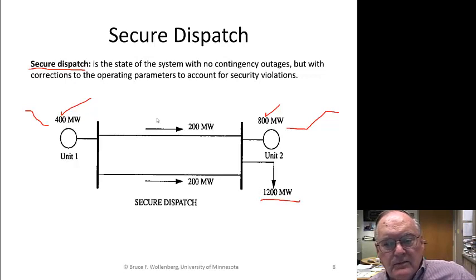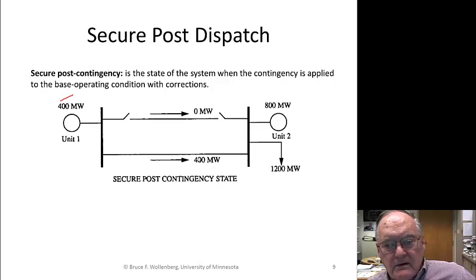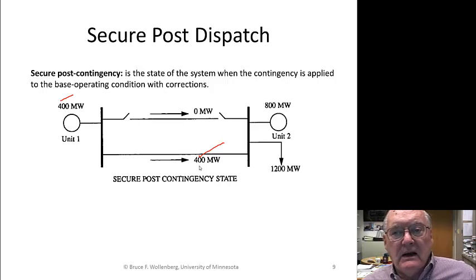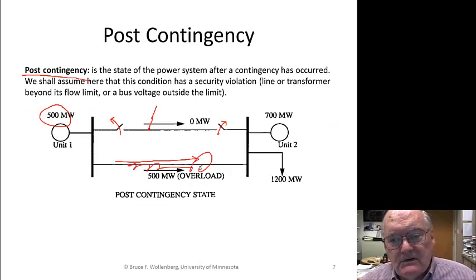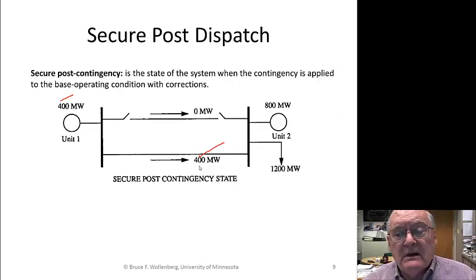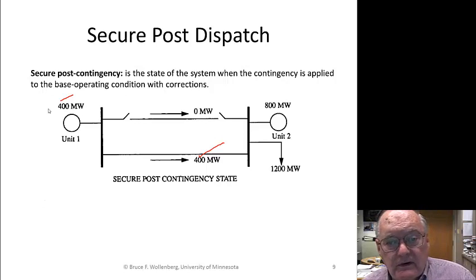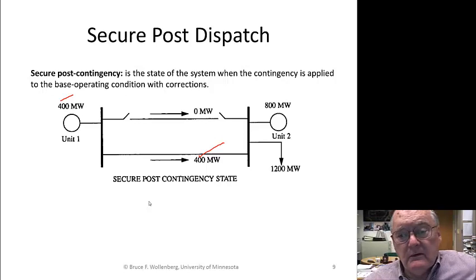I'm still supplying the load, but now if I get an outage like this, then I'm at 400 here, and I'm at 400 here. I don't have any overload. I'm secure. So I have a secure post dispatch. So there's your conditions, again, going from the post contingency that would be detected by the contingency or the what-if analysis. Then I do a secure dispatch, and I can test it again, and the secure dispatch says that in fact things are safe now. It very, very likely may be that this is more expensive than the one where I had 500 over here, and so the cost is greater.